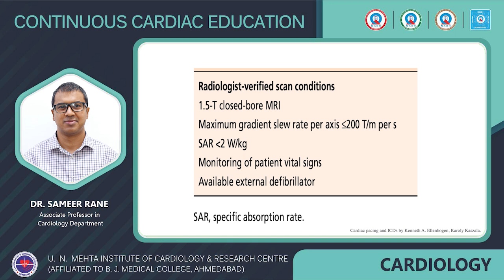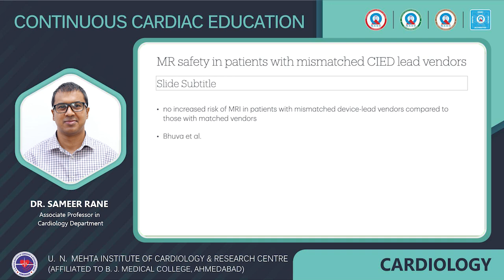Then there are certain scenarios where the MRI safety is not known, in patients with mismatched cardiac implantable electronic device and lead vendors. The CIED system as a whole, even if individual components are classified as MR conditional, may fall outside of labeling if the patients have a mismatched CIED, basically pulse generator and lead vendor. An example is when you have a lead of Medtronic and you are connecting a pulse generator of Abbott or some other company, or vice versa. Then there was a study by Bhuva et al. which showed no increased risk of an MRI in patients with mismatched device lead vendors. Similar small studies have also shown consistent reports. While these studies may be encouraging, it should be noted that they do not cover all potential combinations and permutations of such mismatches.